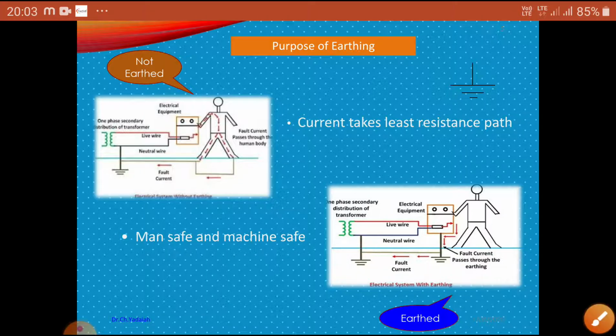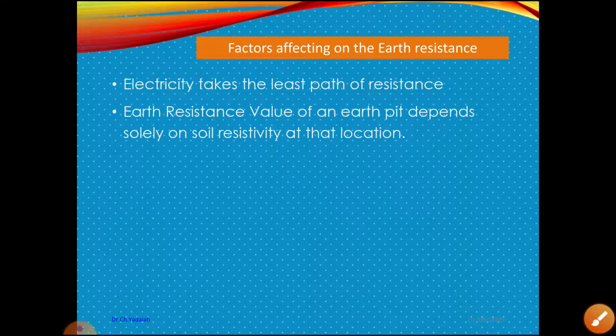Electricity takes the least path of resistance. You know that with low resistance, the current will be more, as per Ohm's law. The earth resistance value of an earth pit depends solely on the soil resistance at that location, the temperature of the soil, the soil condition, the moisture content in the soil, the size of the earth electrode used, and the depth of the electrode in the soil. These are some factors that influence the earth resistance of the system. Remember these factors, dear students.